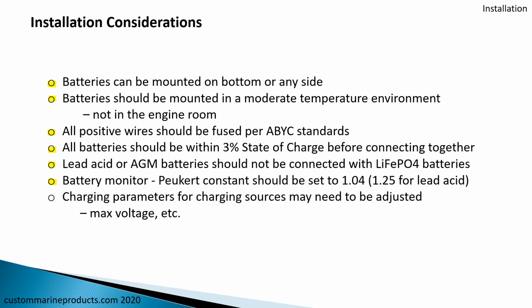These battery monitors typically program for lead acid with a Peukert constant of about 1.25, and that compensates for the inefficiencies in charging the battery. Because lithium iron phosphate is so much more efficient than lead acid, you'll want to change your scale in your battery monitor to 1.04 or even 1.03 so that the battery monitor is not compensating for this tremendous inefficiency that lead acid batteries have. You may also need to change some of the charging parameters in your charging sources.